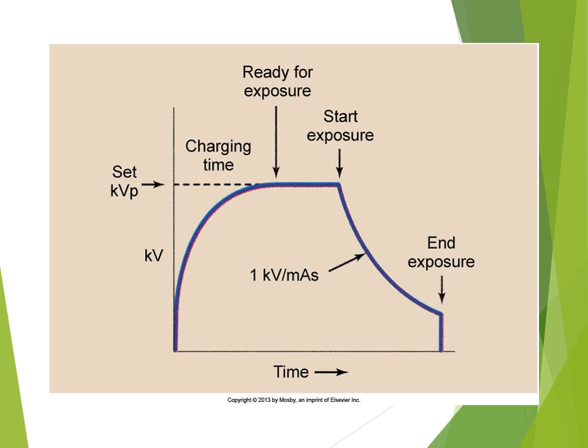And so this is just showing that we have a set exposure kVp. We're ready for the exposure. We start the exposure and then we end it, but there's this period of time where the leakage is going to happen. This can also be used for chest units too, for use for just chest X-rays only.